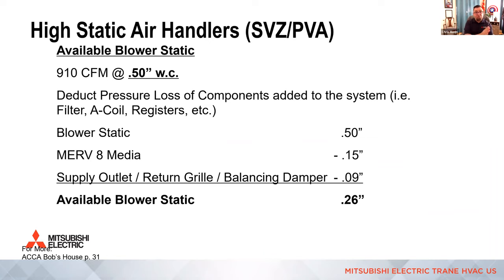All right, so in this example, I chose that 910 CFM and 0.5 inch of static. And then we do the exact same process, but we're obviously going to be servicing a whole floor with this size air handler, or this size system. So we start with the available blower static and we deduct the devices we're adding to the unit in the longest run. So a MERV 8 media filter. And that same MERV 8 might be 16 by 25, 4 or 5 inch pleated, right? Or 20 by 25, right?